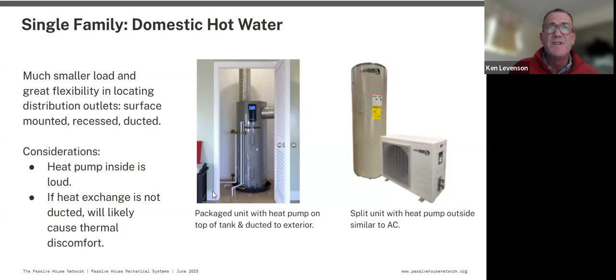We have a split system where you can have the outside unit and the inside tank, or a single unit. The trick is we don't want the hot water heater cooling the interior environment. It's much better to duct the intake and exhaust air, keeping the space isolated and the ducts insulated. It's also a big noise issue, but you can certainly do it.